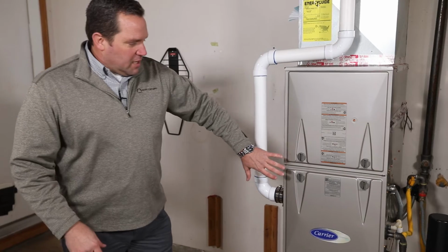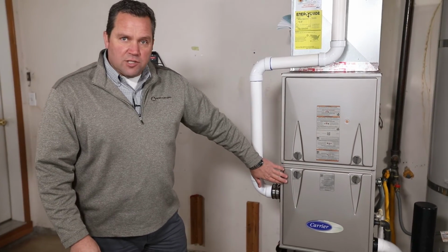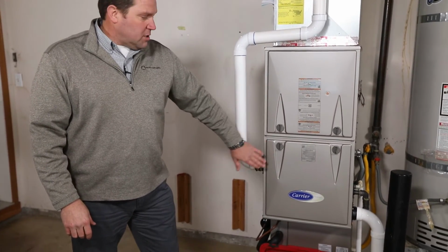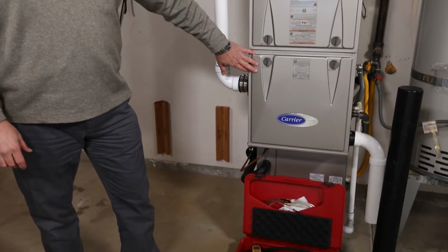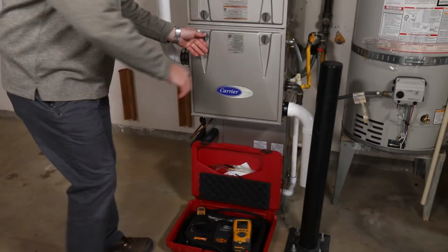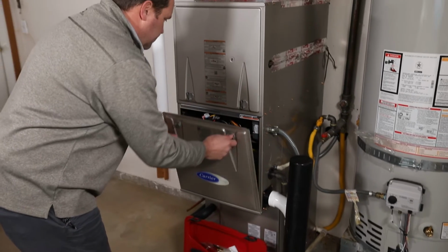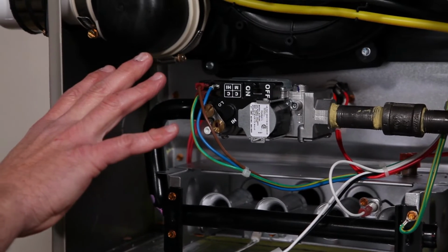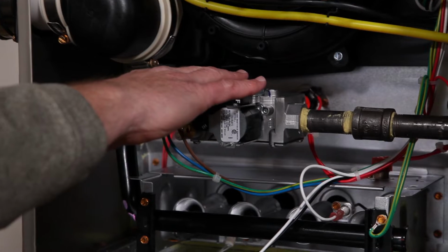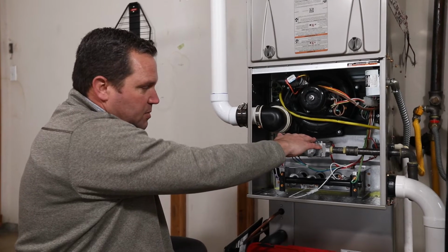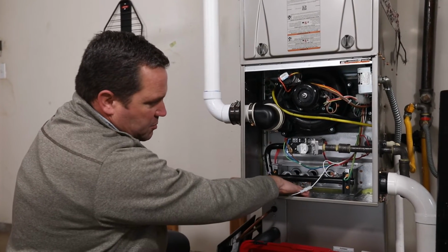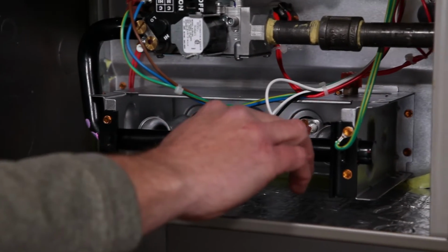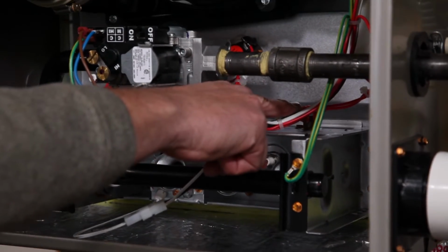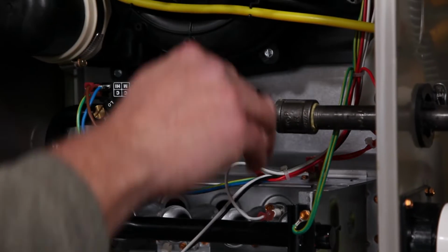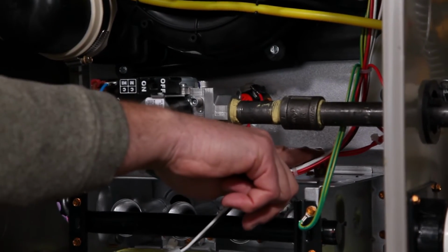So what we have here today is a Carrier gas furnace. This is a Performance Series gas furnace, 95% efficiency. And so what I'll do is I'll go ahead and take the doors off. In our gas furnace, we've got our gas valve, which controls the flow of gas into the system. We've got our igniter, which is back in here. We've got our flame sensor right here on the right. And then we've got our high limit control back here.